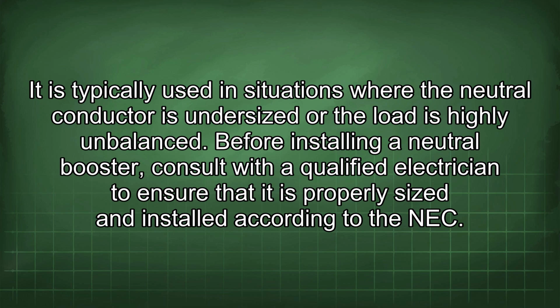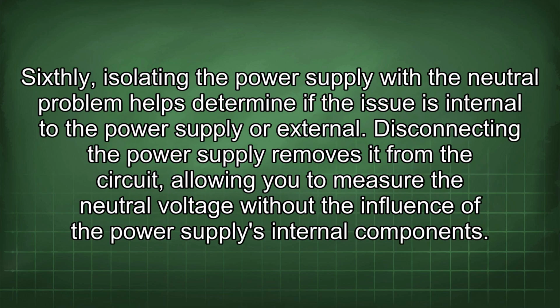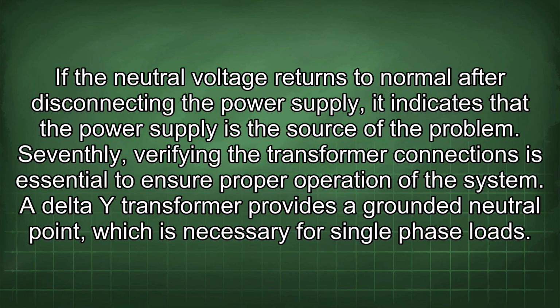to the NEC. Sixthly, isolating the power supply with the neutral problem helps determine if the issue is internal to the power supply or external. Disconnecting the power supply removes it from the circuit, allowing you to measure the neutral voltage without the influence of the power supply's internal components.